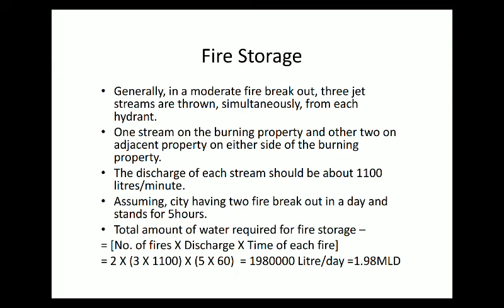Number of fires we are assuming 2, and discharge is 3 jets with 1100 liters per minute, into time of each fire, that is 5 into 60, 5 hours into 60 minutes. We are converting this into minutes, as the discharge is in liters per minute. So the total amount is coming 19 lakhs 80,000 liter per day, that is 1.98 MLD. That part is required per day.